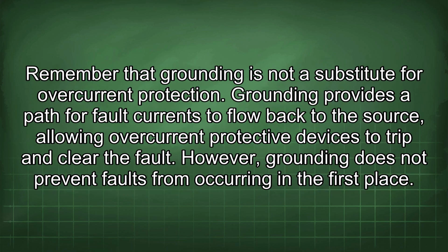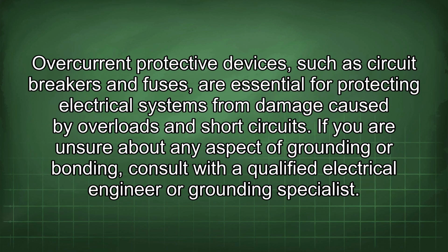Remember that grounding is not a substitute for overcurrent protection. Grounding provides a path for fault currents to flow back to the source, allowing overcurrent protective devices to trip and clear the fault. However, grounding does not prevent faults from occurring in the first place.